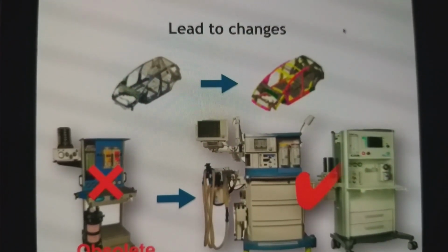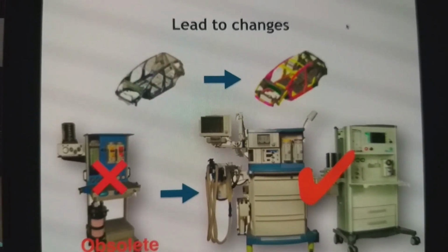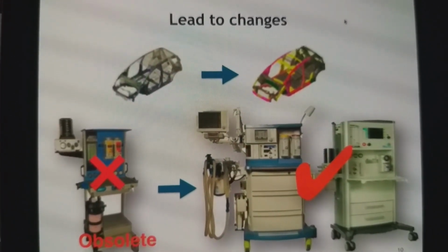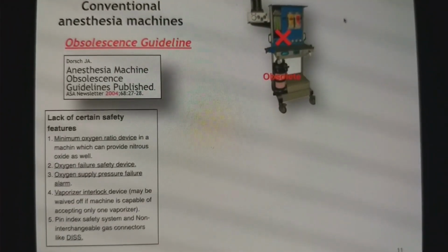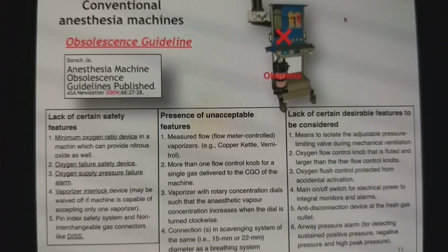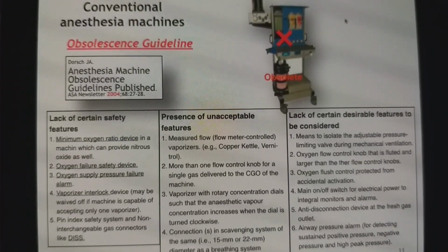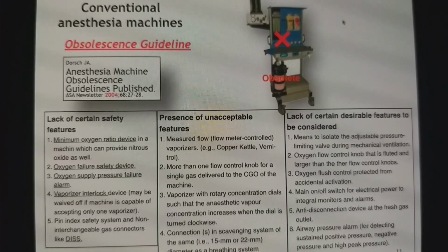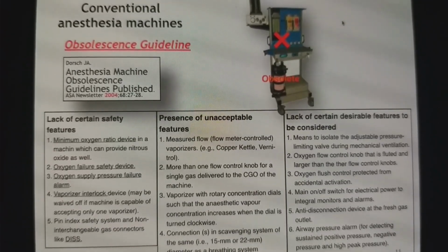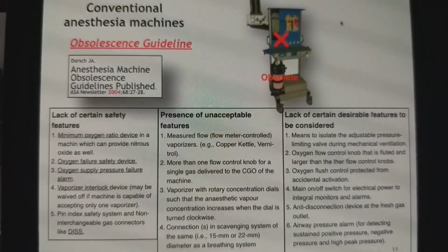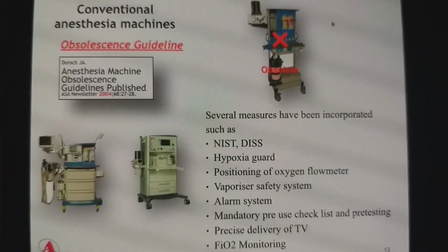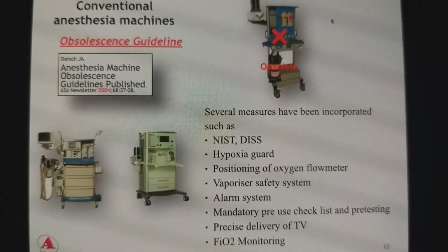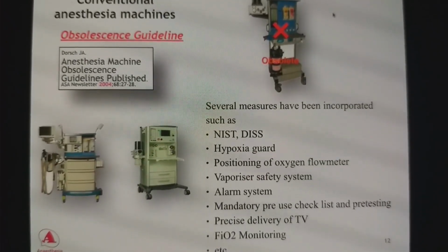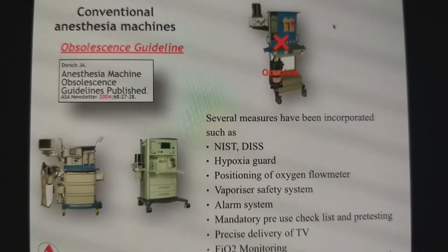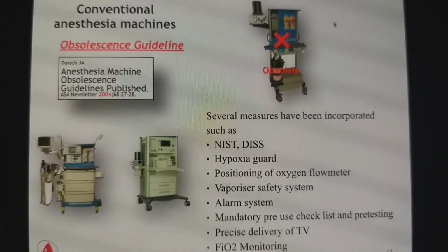And this led to changes in the anesthesia machine. We started from the simple Boyle's apparatus, or simple Boyle's machine, and these workstations were designed. In fact, obsolescence guidelines were published in 2004, where lack of certain features, presence of unacceptable features, or lack of certain desirable features were considered, and on that basis machines were made obsolete and some new features were added, like hypoxia guard, positioning of oxygen flow meter, safety system, alarm system, mandatory pre-use checklist, precise delivery, and so much more. There were so many changes addressed in your anesthesia workstation.